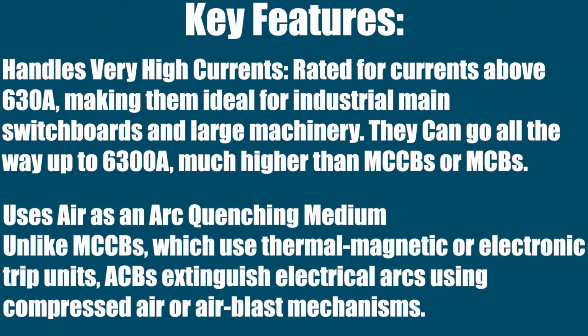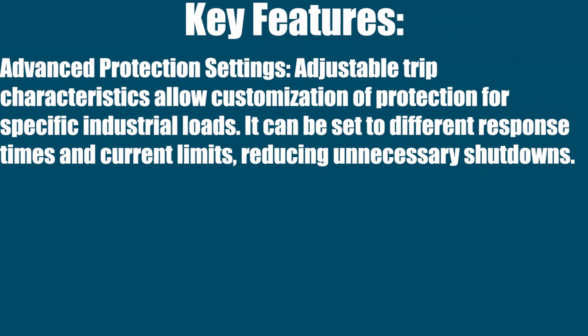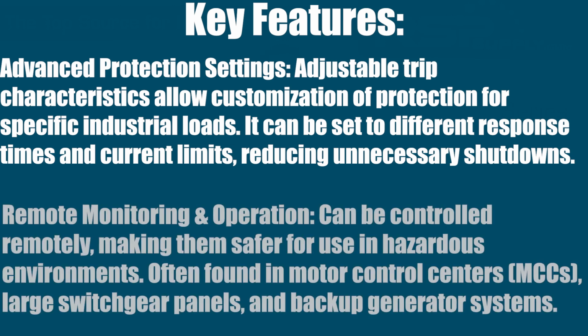They use air as an arc quenching medium. Unlike molded case circuit breakers, which use thermal magnetic or electronic trip units, air circuit breakers extinguish electrical arcs using compressed air or air blast mechanisms. Let's talk about some of their advanced protection settings. They offer adjustable trip characteristics that allow customization of protection for specific industrial loads. They can be set to different response times and current limits, and this reduces unnecessary nuisance shutdowns or trips. Remote monitoring and operation is another strength of ACBs. They can be controlled remotely, which makes them a lot safer for use in hazardous environments. You'll often find them in motor control centers, large switchgear panels, and in backup generator systems.